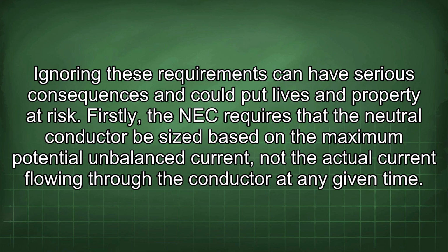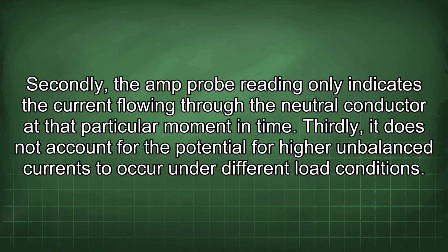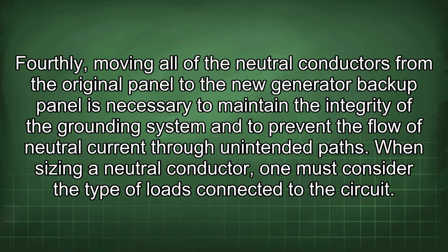Firstly, the NEC requires that the neutral conductor be sized based on the maximum potential unbalanced current, not the actual current flowing through the conductor at any given time. Secondly, the amp probe reading only indicates the current flowing through the neutral conductor at that particular moment in time. Thirdly, it does not account for the potential for higher unbalanced currents to occur under different load conditions. Fourthly, moving all of the neutral conductors from the original panel to the new generator backup panel is necessary to maintain the integrity of the grounding system and to prevent the flow of neutral current through unintended paths.